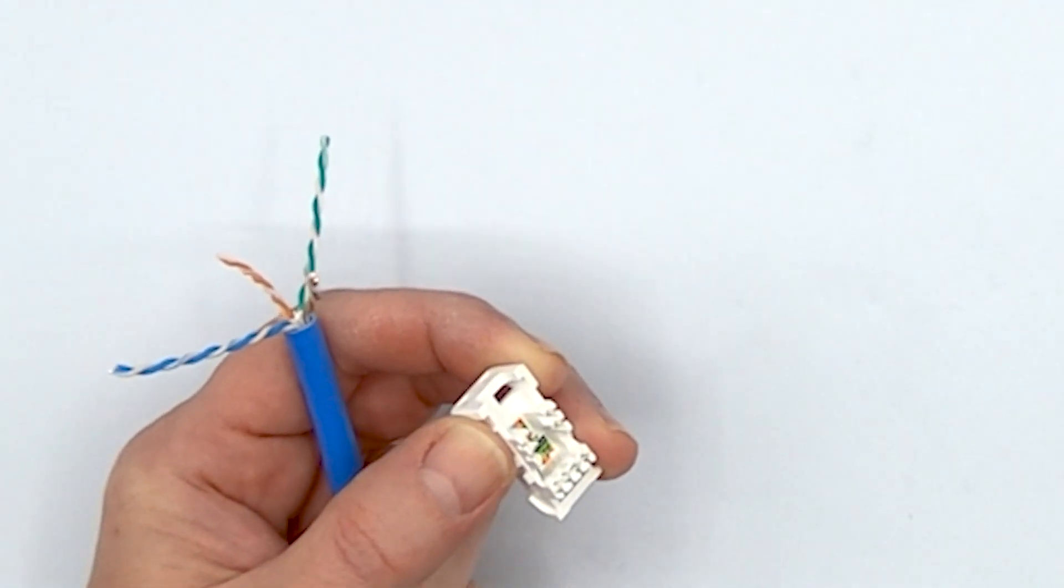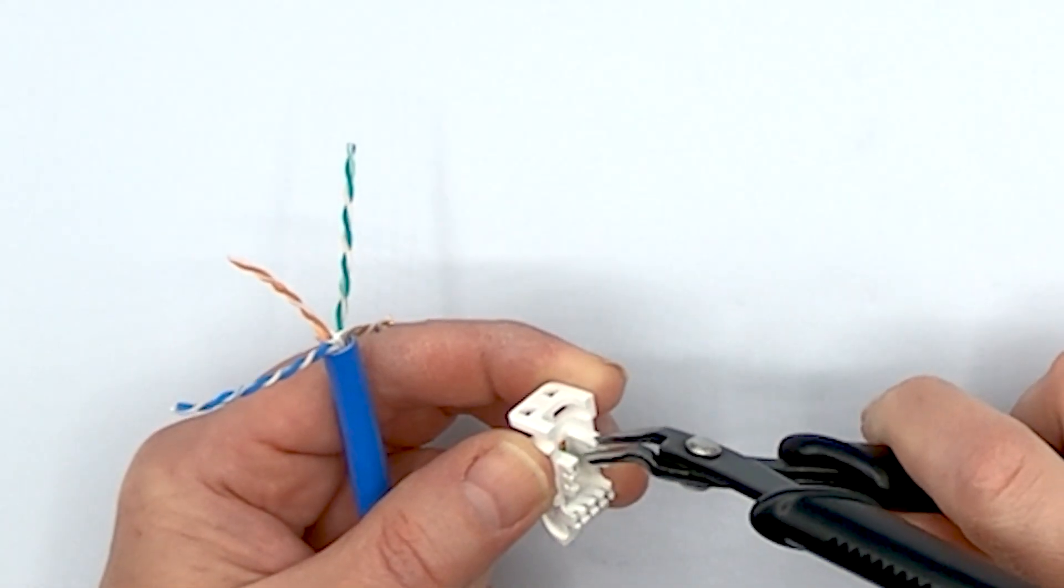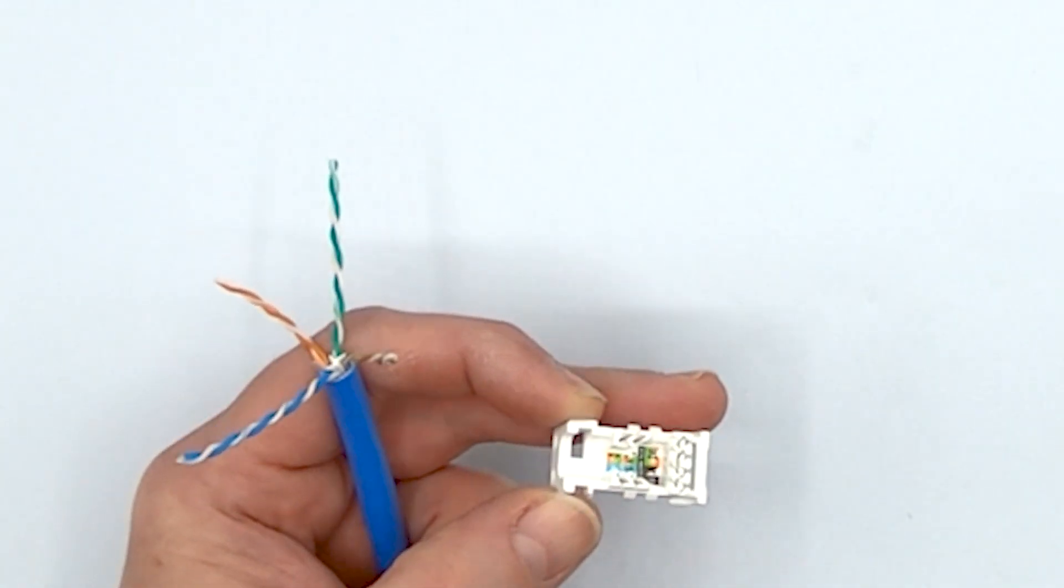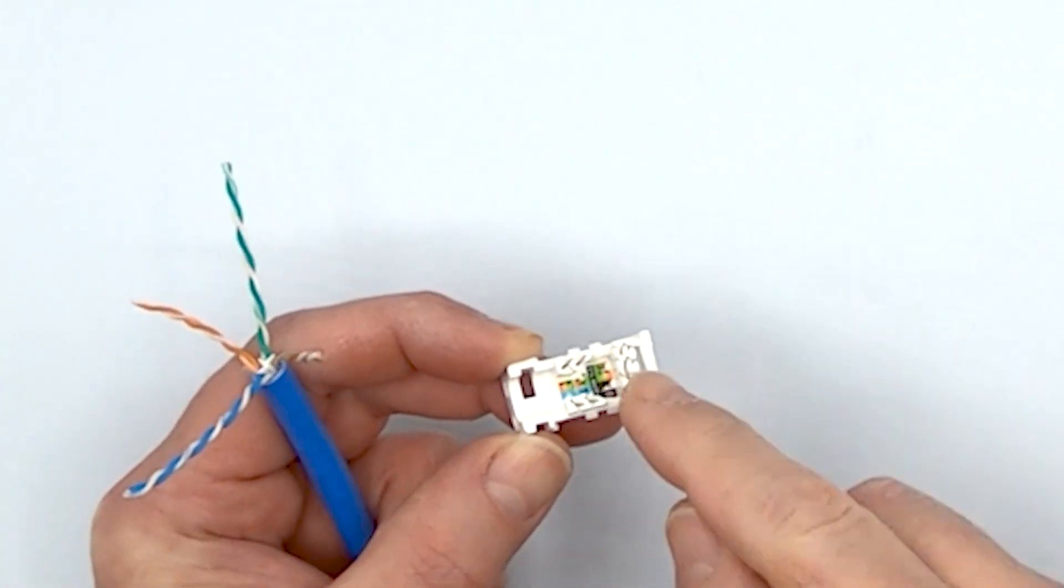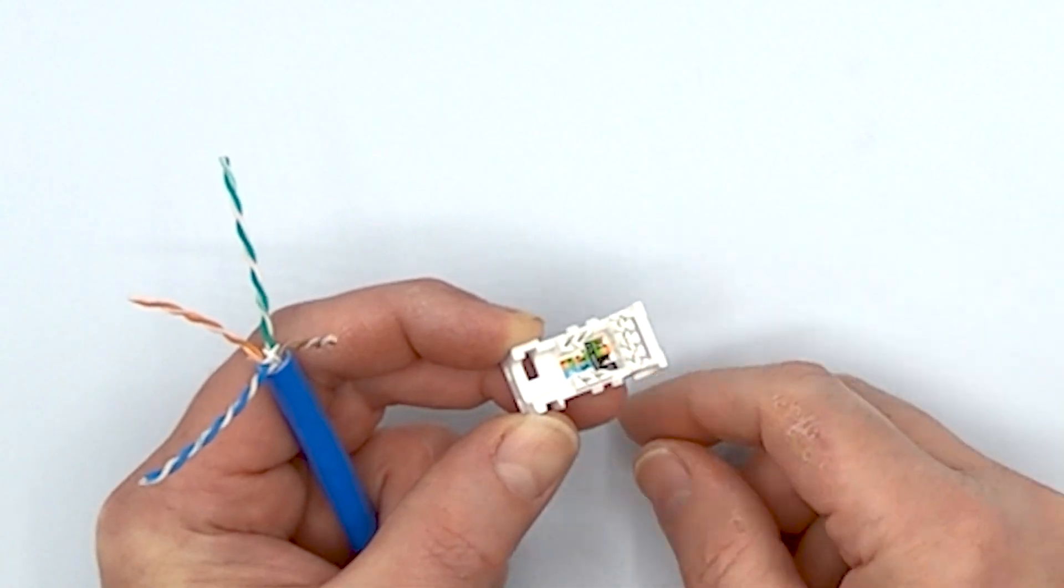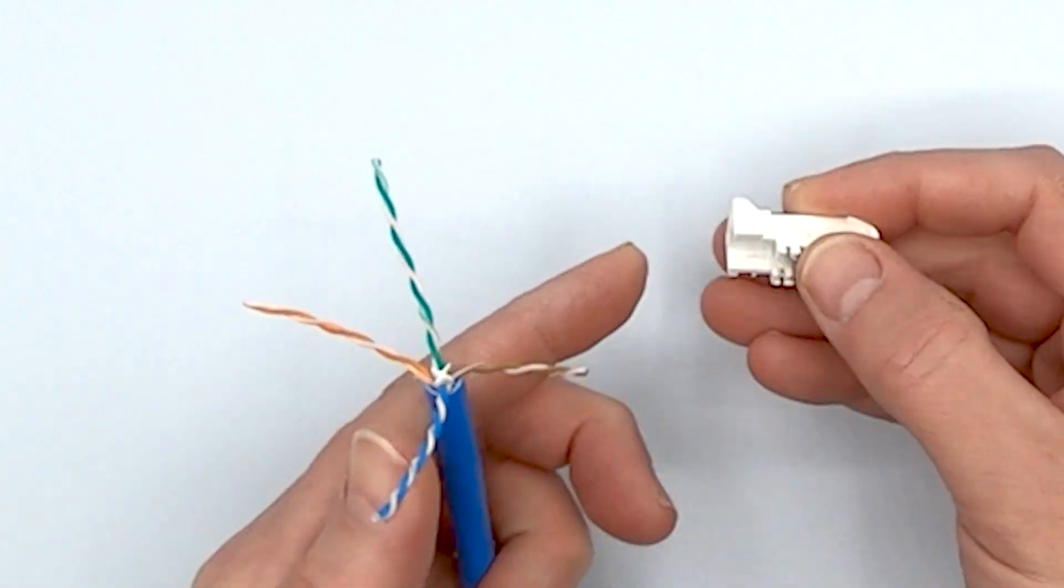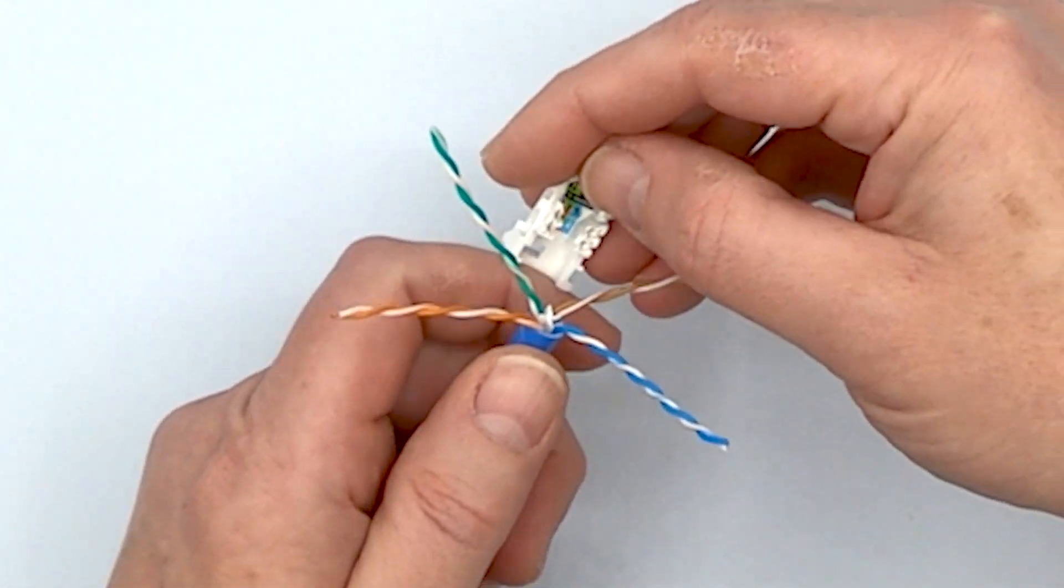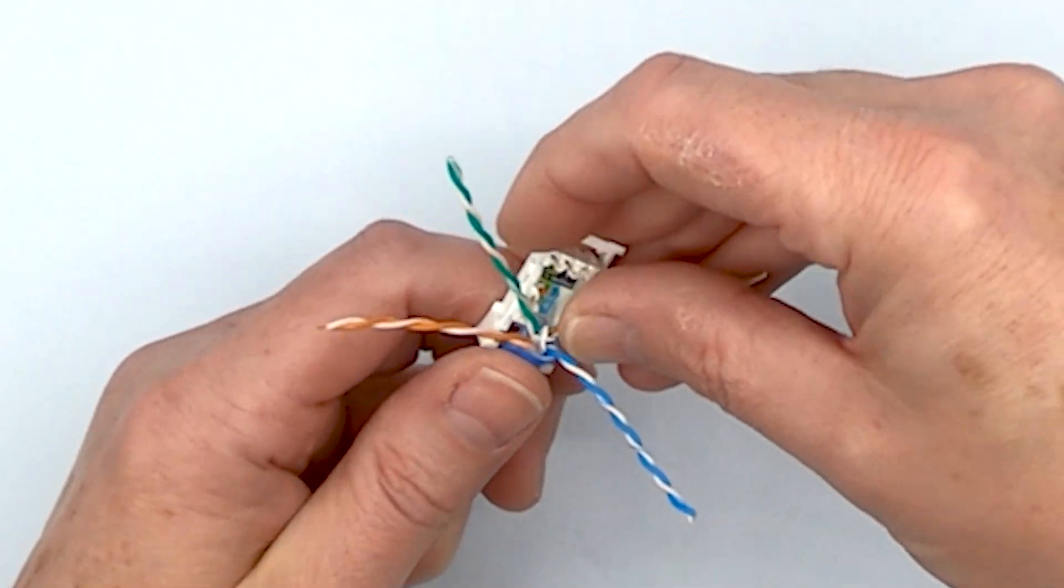The reason why is because that stop point helps set the half inch maximum untwist that you can have inside this conductor holder cap to maintain performance. So we know that blue is going first at the back here. We're going to untwist that pretty well all the way down.